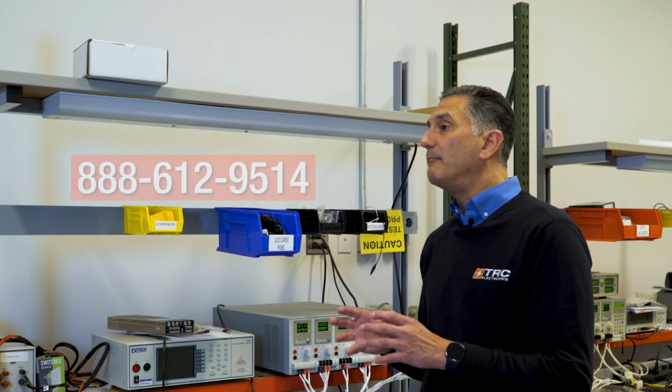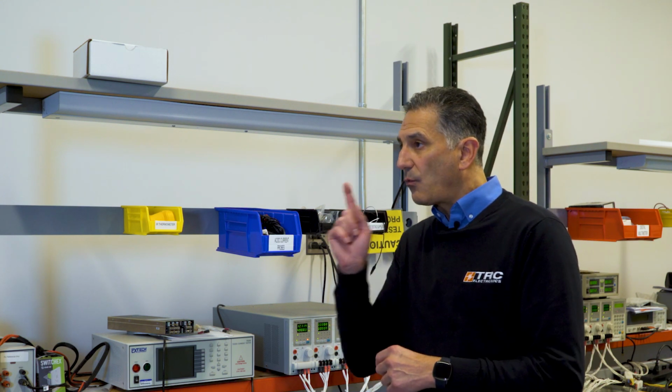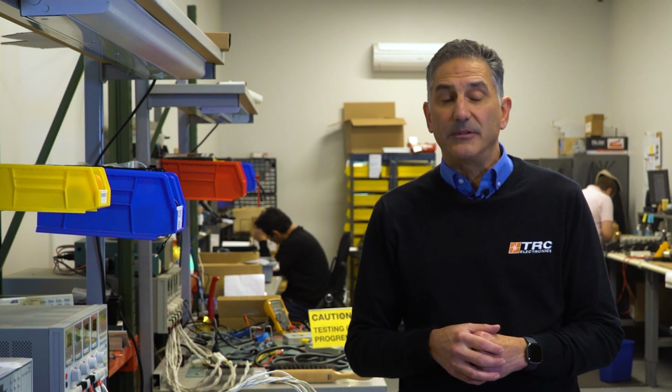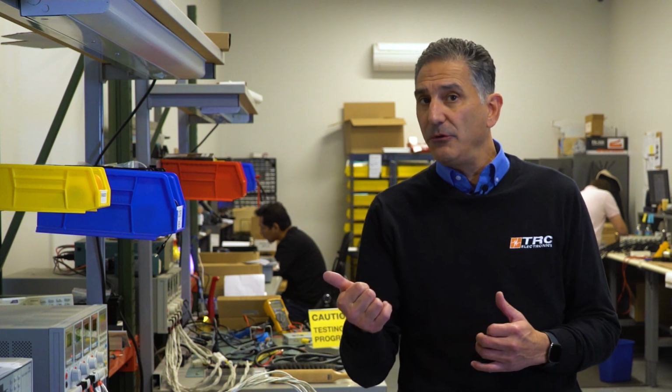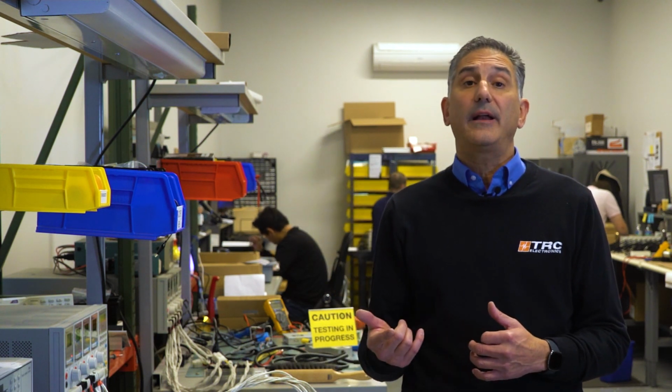So let me explain the downsides of constant current. Suppose you have a system where you have multiple loads connected to one output. So you could have a 20 amp load being connected to 10 2 amp outputs. If you were to have a short circuit on one of those 2 amp outputs, you could potentially have 20 amps going to that short circuit point and actually have a fire if you do not have a fuse in line, or if you do not have the right wire selected for 20 amps.